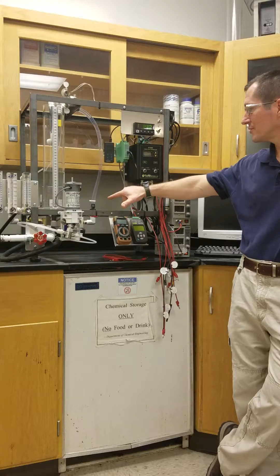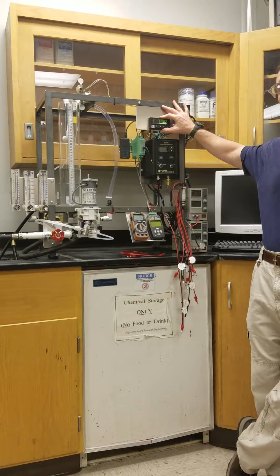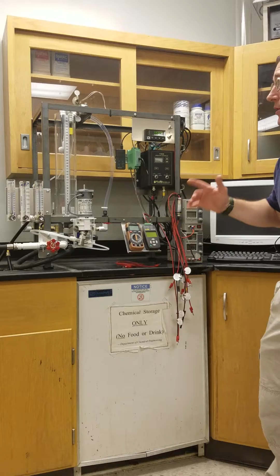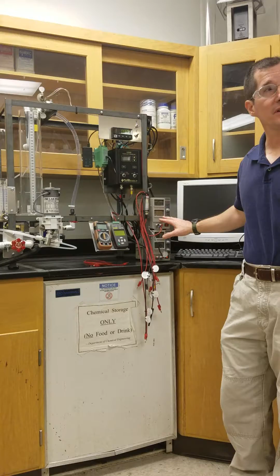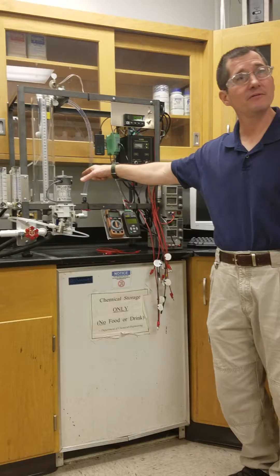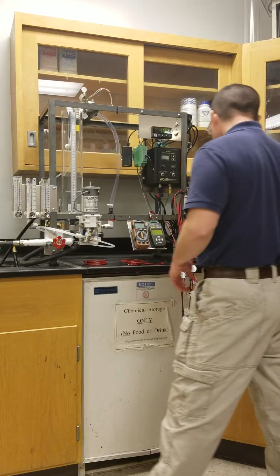So you have your pressure transducer that then goes to this device. Based on that measurement, this device makes a control decision on how to change the output to the control valve. Now for the first part of this experiment, we're not going to be using this controller at all. You're going to be doing it manually, okay, with a DC power supply. So we can mimic sending a 4 to 20 milliamp signal to this control valve using a power supply.